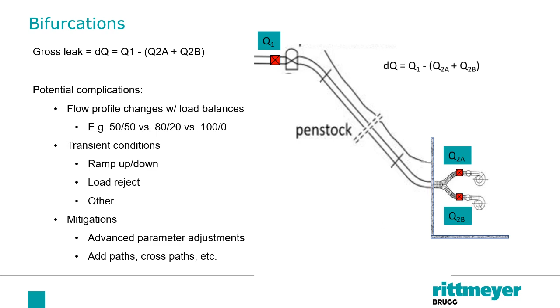The lower flow meter is in a good, or at least better, measurement location, and in generate mode will often give decent results. However, when you turn around to pump mode, now this lower flow meter is in a very poor location near a pump, whereas this upper flow meter, at least in this example, is in an excellent location. So if you calibrate for, say, the generate mode, the pump mode can now be quite a bit off, even worse than if you hadn't calibrated it sometimes. So getting these two modes to balance out can be a real trick.